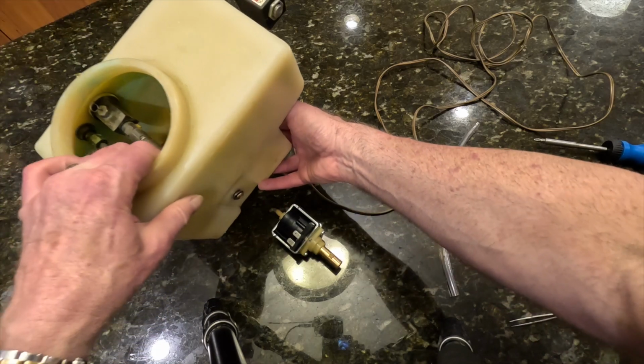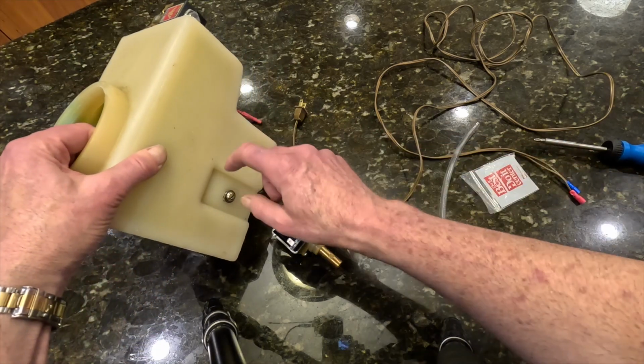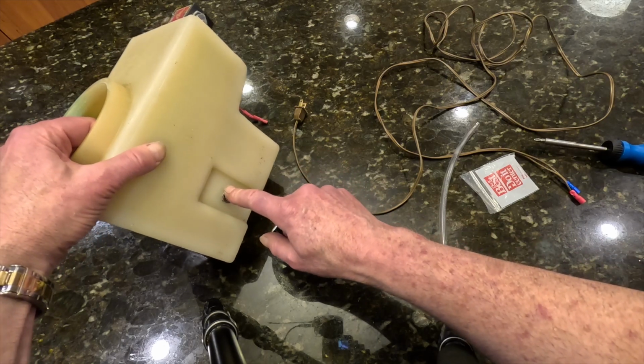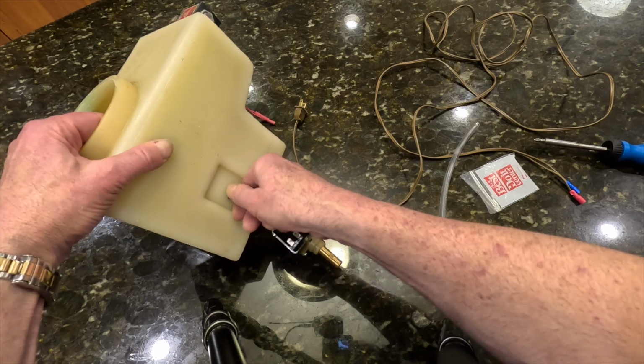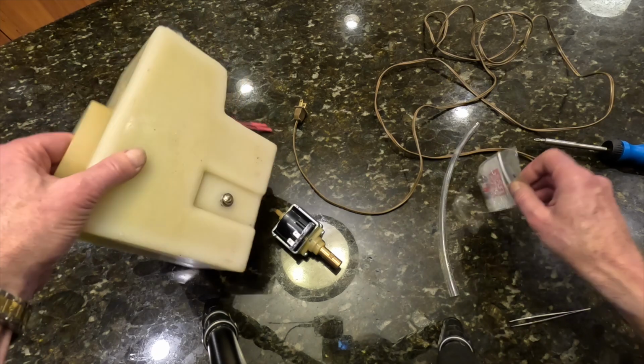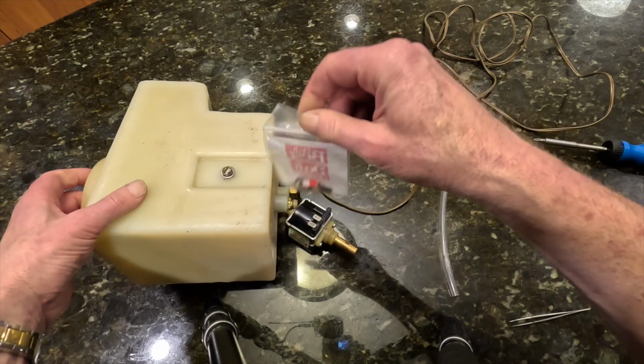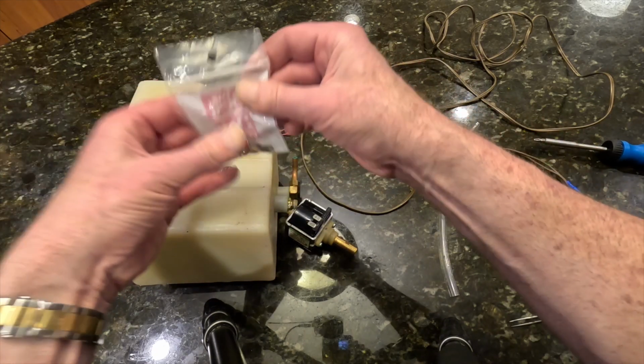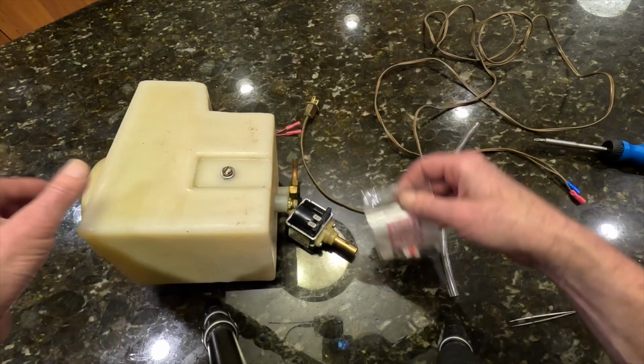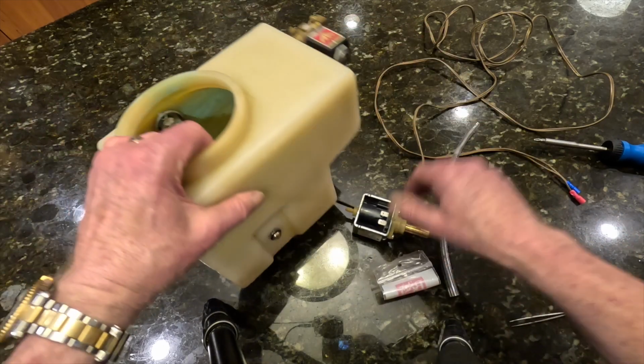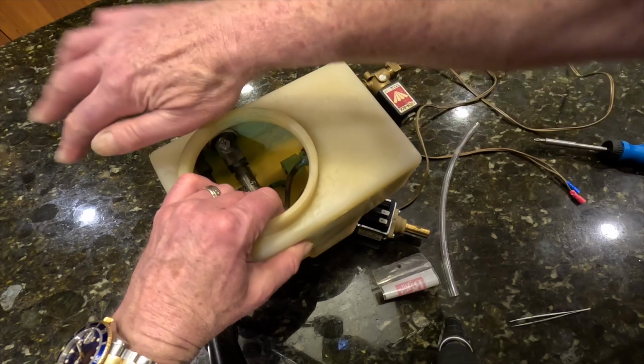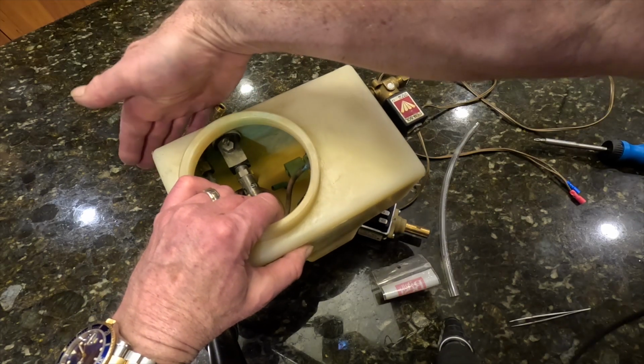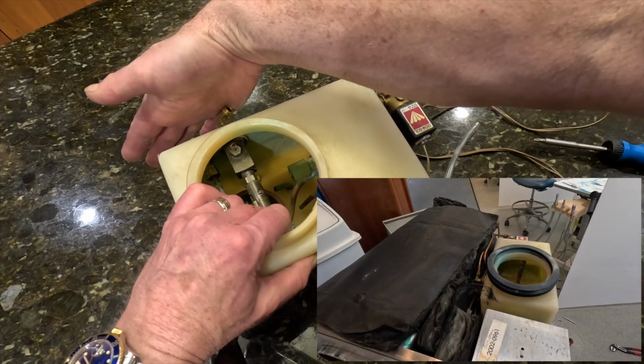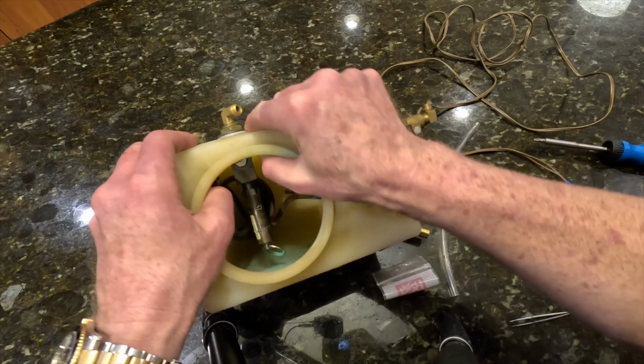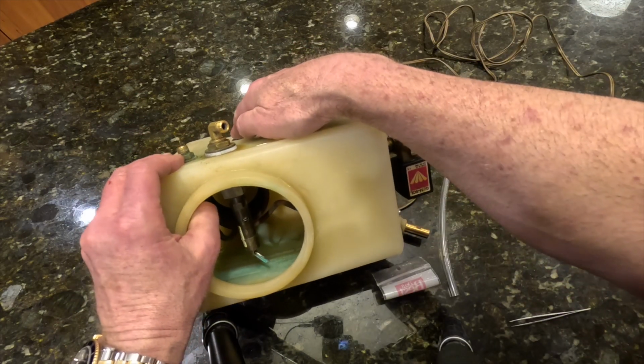Now, what was really rough to get off was this was held on by 2 screws like this. They were regular, not Phillips, they were flat-headed screws. The one on the outside was very easy to get to. The one on the inside was right up against, picture this, the sterilization chamber is right here, about this close, it's pretty much touching, so there was no way to get way down here to a screw.